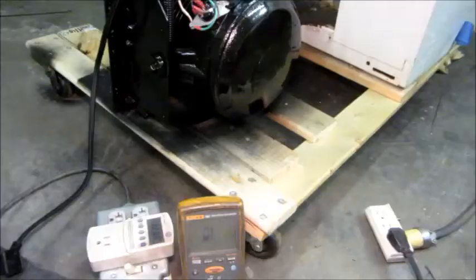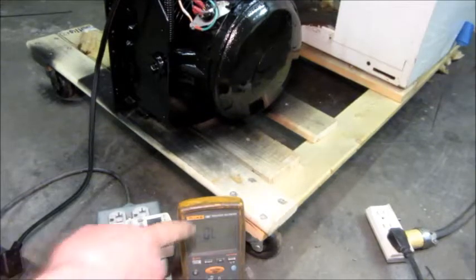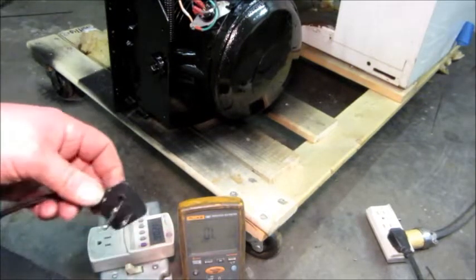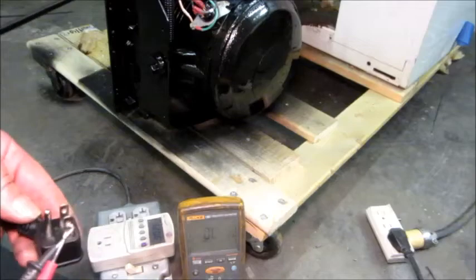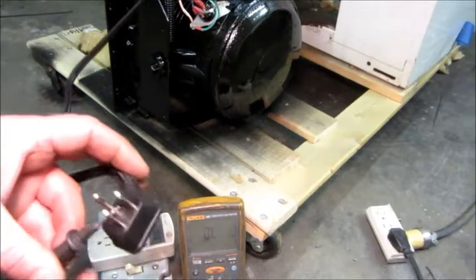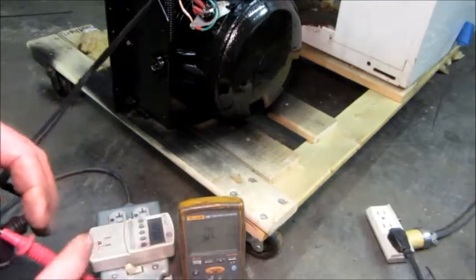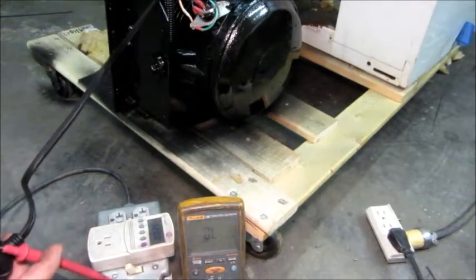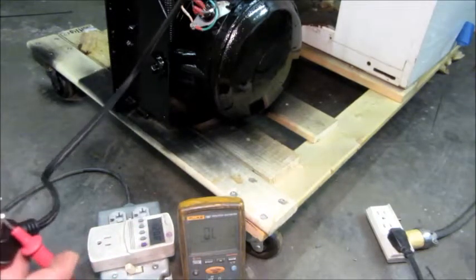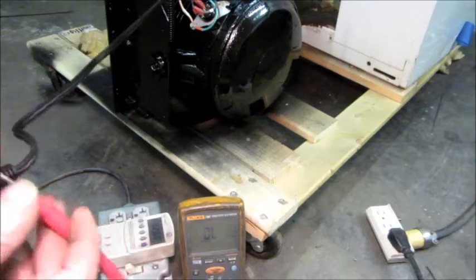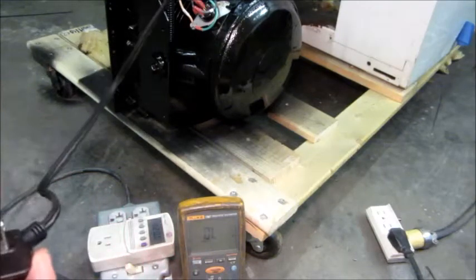So the door is closed and the thermostat is turned off. And what that means is there should be no continuity on the plug. So you can see the meter there on resistance mode. I take the new power cord. I'm going to check from one of the power input pins to the other one. And you see it shows on the meter OL, which means there's no connection, which is good because the thermostat's off and the door's closed, so the light's off.